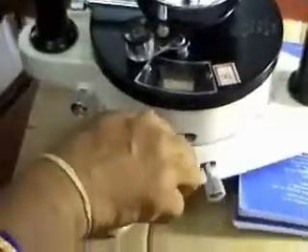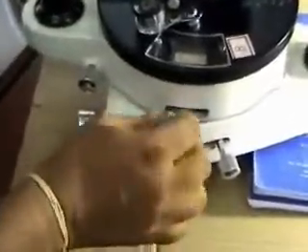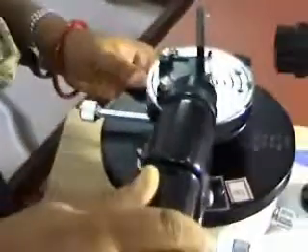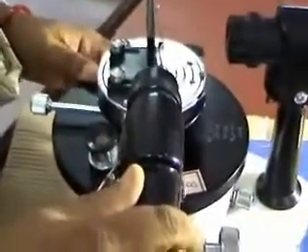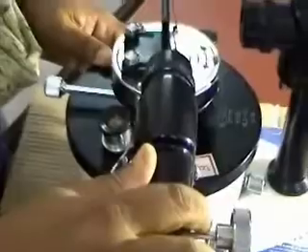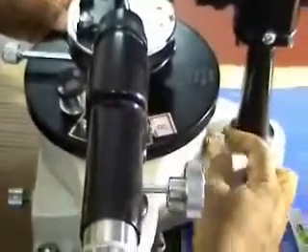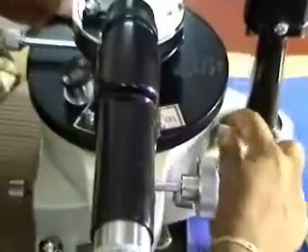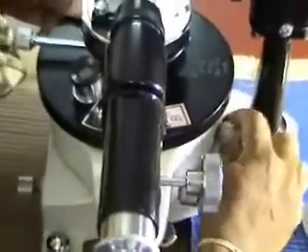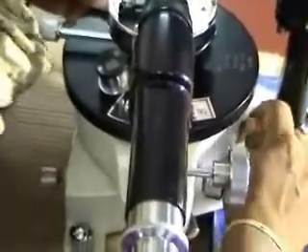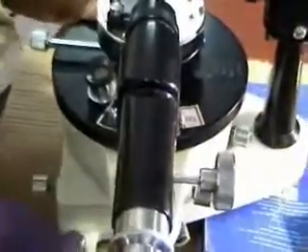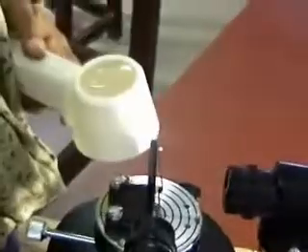We loosen the telescope main screw and keep it so that the vernier reads 90 degrees. Don't bother about the other side of the vernier. See the 0 side and keep it at 90, 0. First tighten the main screw, then using the lens see if it is at exact 90.